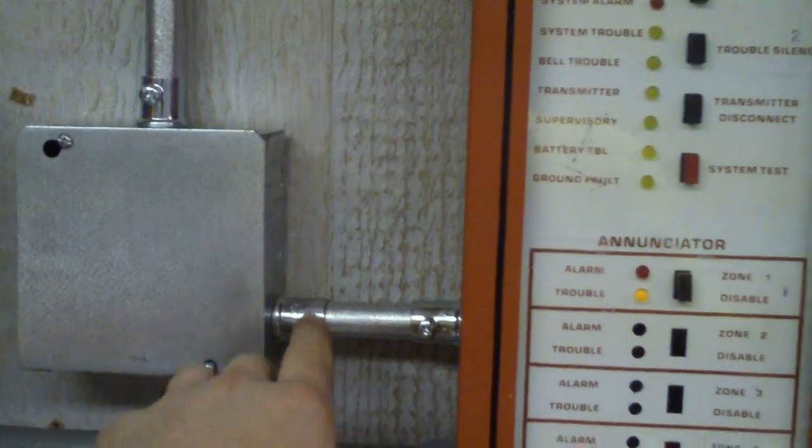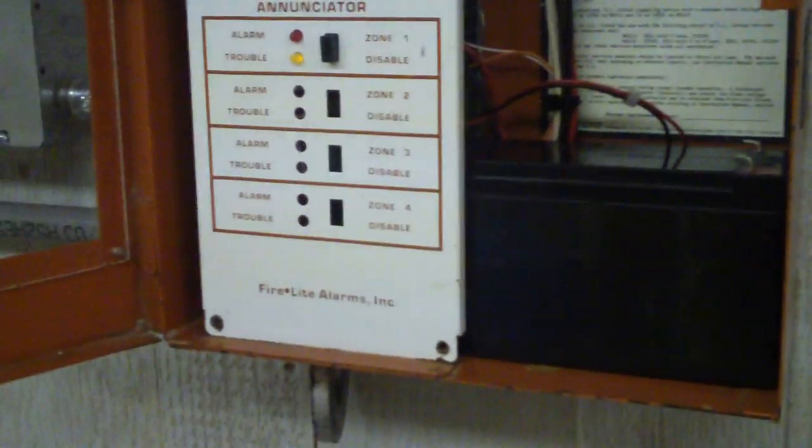This is half inch EMT. I'm using set screw connectors and if we open up the panel you'll see that I have these PVC bushings if you want to call it that, and these are required by code so your wires don't get cut by the connectors.